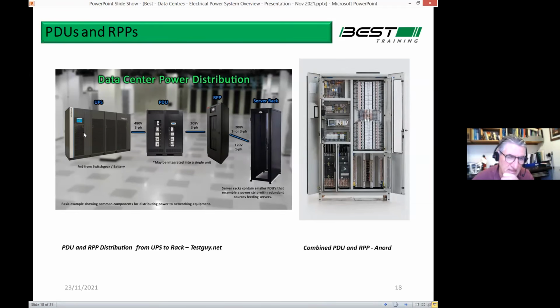So you have the UPS here, and what we're looking at is how do you get power from the UPS to the server. So you don't just bring big heavy cables, you have to go through a series of switchgear systems to get there. So in America, they talk about PDUs, which means power distribution units, and RPPs, remote power panels, etc.